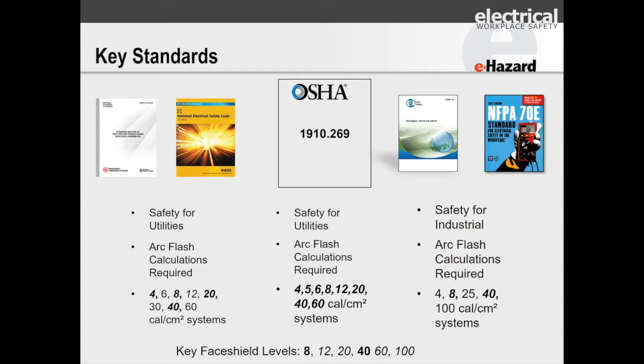Each of these standards have a little different ways of doing things. One of the quick things is, what level of clothing do I need? Well, each of the standards allow 4, 8, and 40 calories as three very critical energy levels of protection that are across the board, and we'll talk about how to apply that in the end. In face shields, your key levels will probably be 8 and 40, although there are some 12s and 20s out there. So there's lots of different things out there.